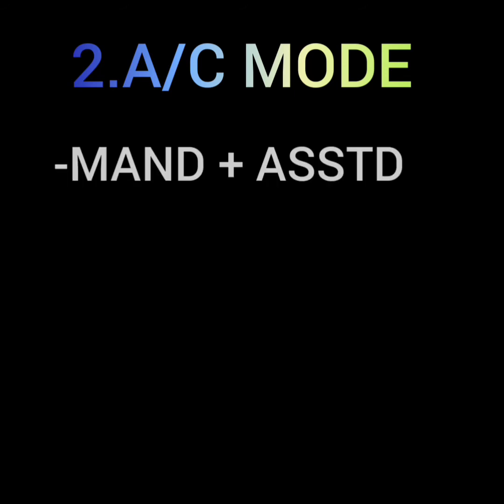It is a combination of mandatory breaths and assisted breaths. Both mandatory and assisted breaths are pressure or volume controlled, but what is the difference between them? The difference lies in whether it is patient triggered or time triggered. That is, whether the patient can initiate the breath or a preset time interval will initiate the breath.